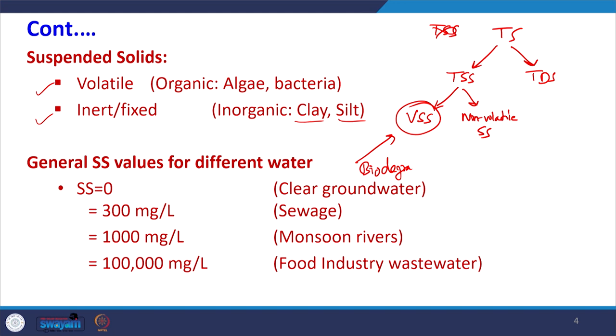VSS is very important. Typical SS values: for clear groundwater it is 0; for sewage it may be up to 300 mg/L; for monsoon river water it can be 1000 mg/L or more; and for food industry wastewater it may be up to 100,000 mg/L. Different types of wastewater have different SS values.